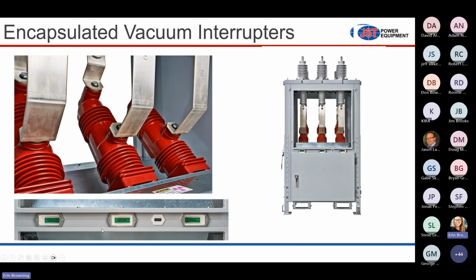Coming back to the slide really quick, I just want to show you these position indicators, open and closed. These are IEEE colored, green for open, red for closed. And then there's an operations counter, and this counter changes on the trip counts. Because if you think about it, when the circuit breaker operates, it's opening. That's the function of the breaker. So this operations counter operates on the trip.